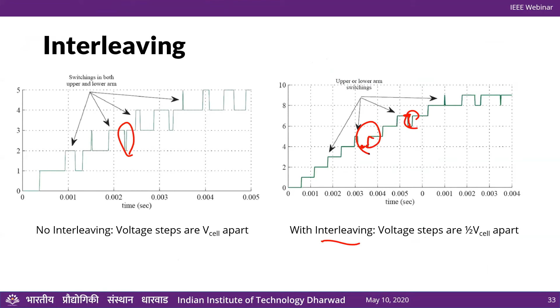You first figure out how many modules need to be turned on at any given instant. For instance, at this point one module needs to be inserted. When one module needs to be inserted, we first figure out whether the current is in a charging direction or discharging direction, because we cannot control that. Based on the current direction, we choose whether the lowest voltage submodule is inserted or the highest voltage submodule is inserted. Essentially, we want to minimize the error between the capacitor voltages and their nominal values.